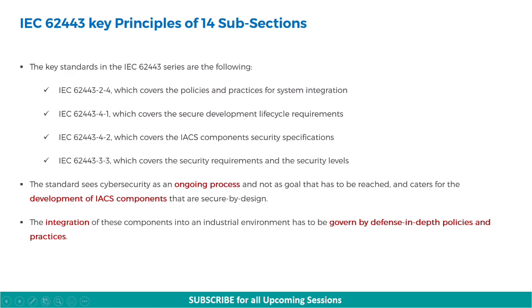Out of the 14 subsections discussed, the key standards in the 62443 series are: 62443.2.4, which covers policies and practices for system integration; 62443.4.1, which covers secure development lifecycle requirements; 62443.4.2, which covers IACS components' security specifications; and 62443.3.3, which covers security requirements and security levels. The standard sees cybersecurity as an ongoing process and not as a goal to be reached, and caters for the development of IACS components that are secure by design. The integration of these components into an industrial environment must be governed by defense-in-depth policies and practices.